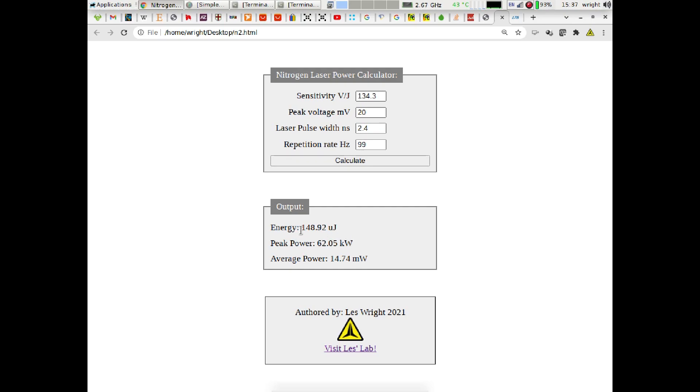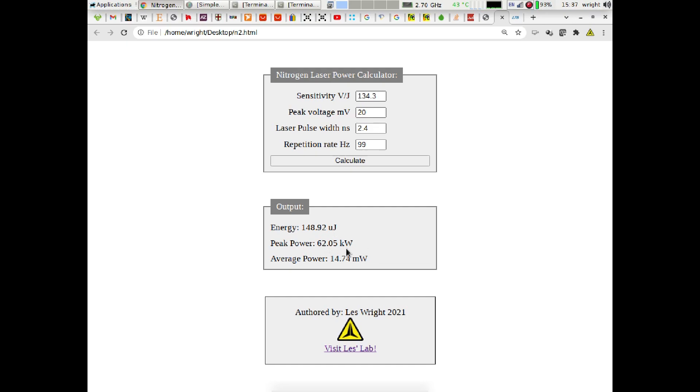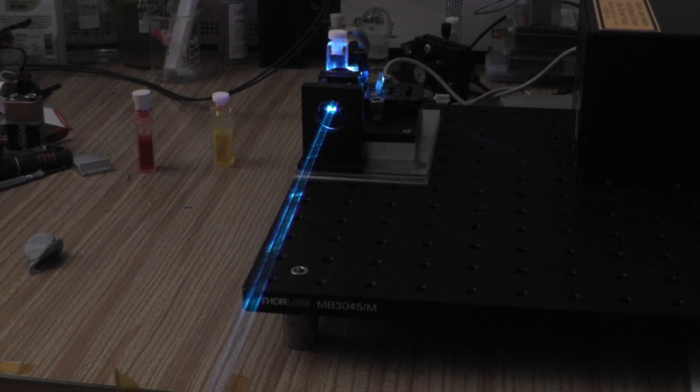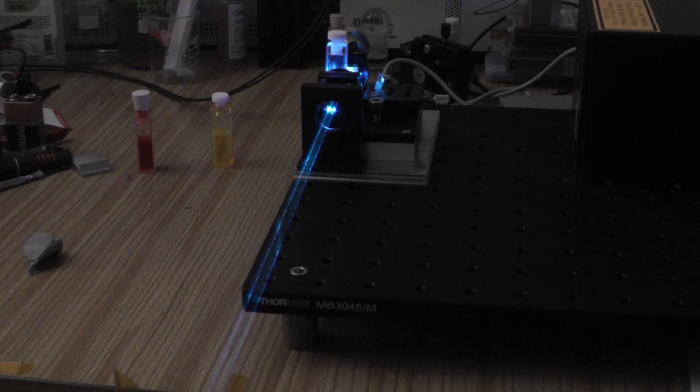And the actual output power is 148.92 microjoules or 149 microjoules per shot, which means that the tube itself is in excellent condition. Normally these tubes are rated to at least put out 140 microjoules after let's say a million shots or so, so really really good. Our peak power is 62 odd kilowatts which seems about right, and our average power at 99 Hertz is almost 15 milliwatts. Absolutely fantastic.